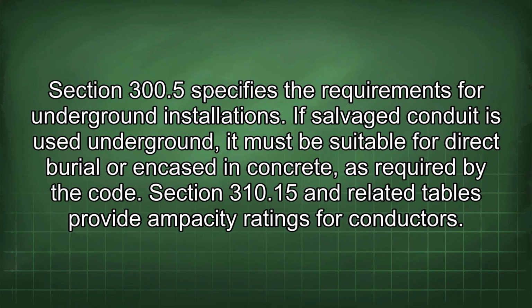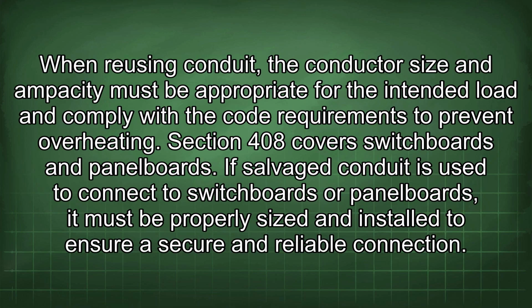Section 300.5 specifies the requirements for underground installations. If salvaged conduit is used underground, it must be suitable for direct burial or encased in concrete, as required by the Code. Section 310.15 and related tables provide ampacity ratings for conductors. When reusing conduit, the conductor size and ampacity must be appropriate for the intended load and comply with the Code requirements to prevent overheating. Section 408 covers switchboards and panelboards. If salvaged conduit is used to connect to switchboards or panelboards, it must be properly sized and installed to ensure a secure and reliable connection.